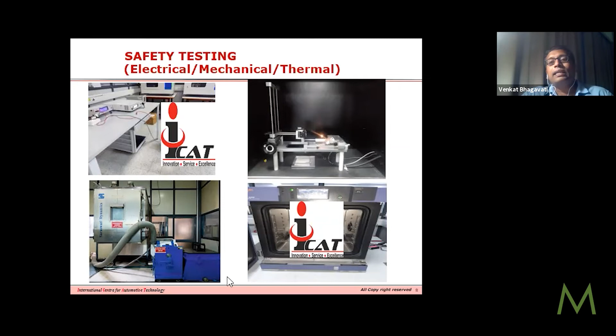Then on the bottom left, you have the vibration shaker. Every device has a vibration testing requirement. Specifically in medical devices, this requirement is there in 60601-1-11, which is for home care equipment. And on the bottom right, there is the humidity chamber. Every device typically undergoes humidity preconditioning.